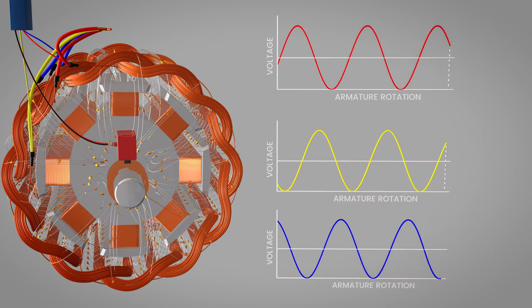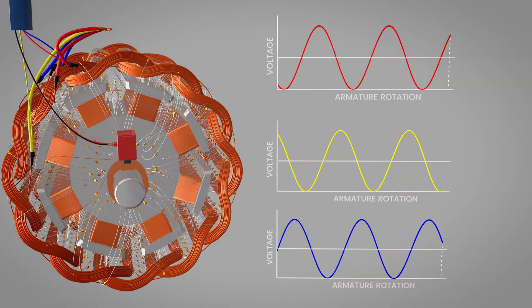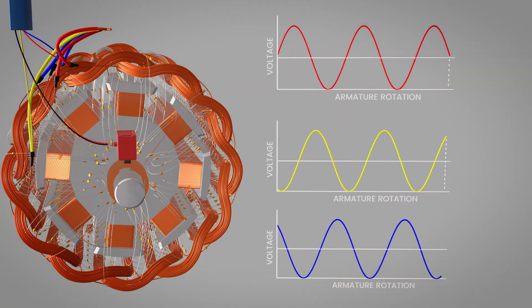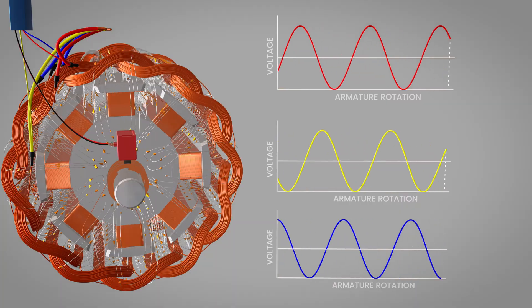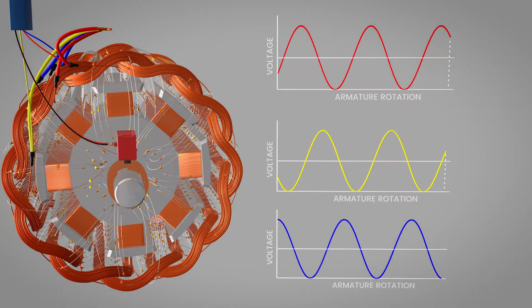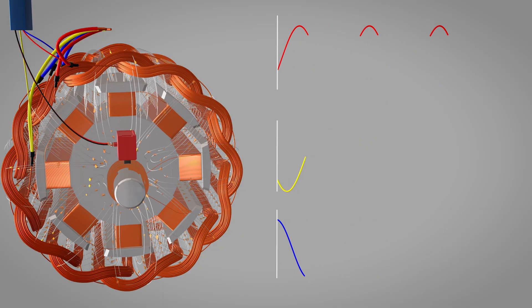If residual magnetism is lost due to prolonged inactivity, demagnetizing influences, or component replacement, the alternator may fail to build up voltage. In such cases, a short burst of external DC excitation is applied to restore residual flux and enable normal self-excitation.